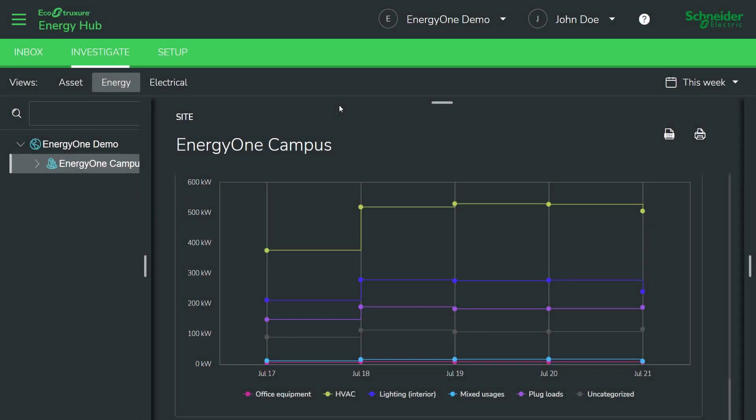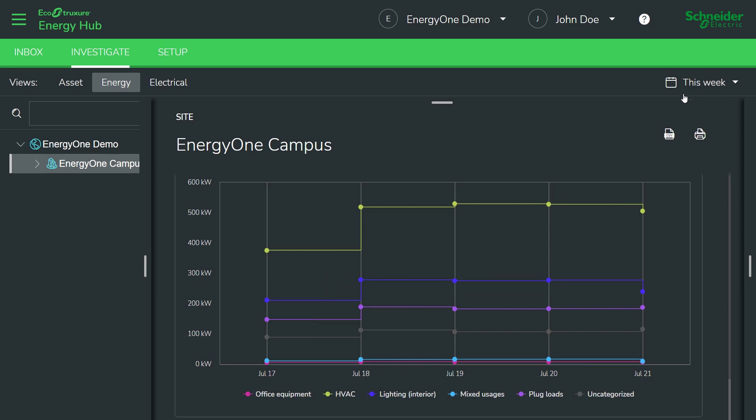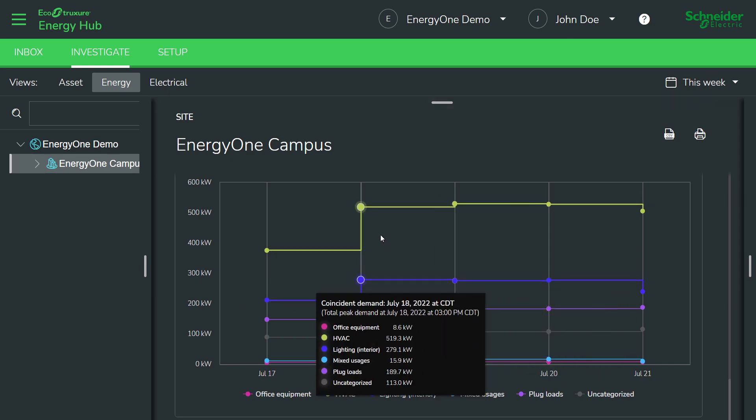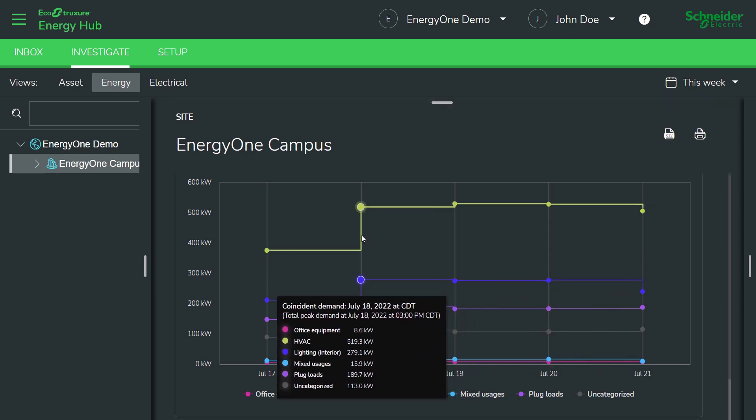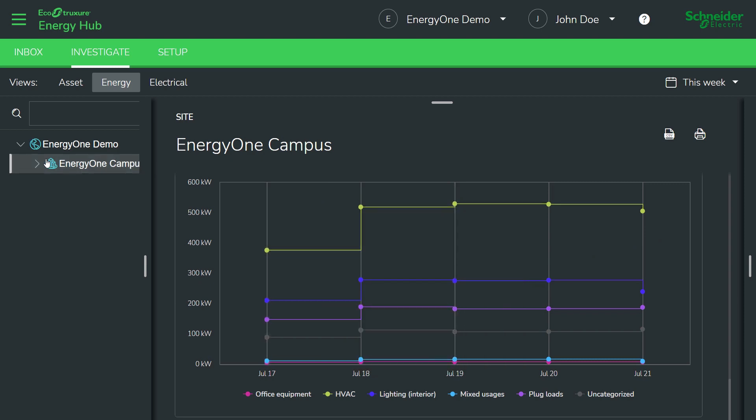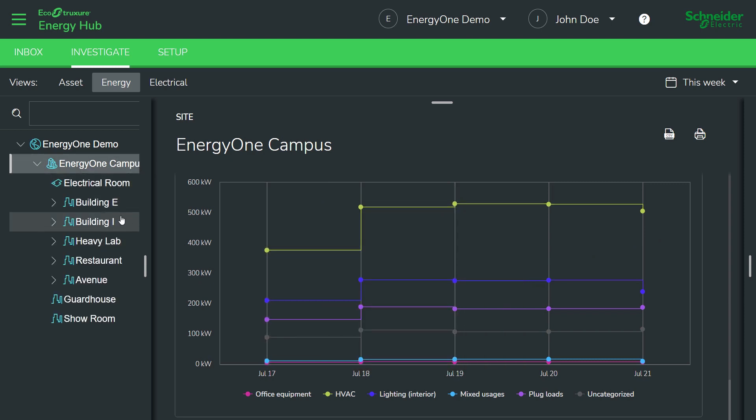Another interesting view is peak demand. So, we can examine peak demand for the period of interest and we can identify what the individual elements that contribute to that demand. Some energy codes like California Title 24 also mandate the collection of peak demand data. So, in this case, HVAC is a big culprit. So, maybe we adjust the building schedule, temperature schedules a little bit to save some peak demand charges. You can also jump to various nodes in the hierarchy to see if there are any particular culprits to that peak demand.